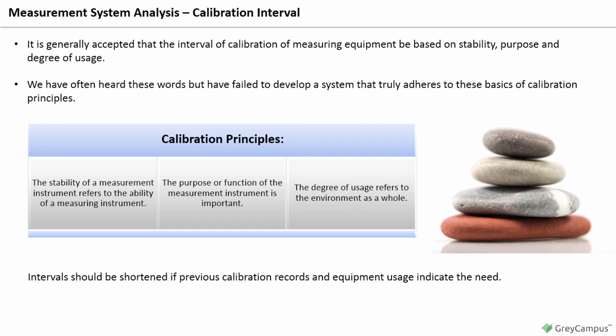A method gaining recent popularity is the verification methodology. This technique requires that very short verification frequencies be established for instruments placed into the system, i.e. shifts, days, weeks, etc. The philosophy behind this system is that a complete calibration will be performed when the measuring instrument cannot be verified to the known standard. This system, when utilized properly, reduces the cost associated with unnecessary scheduled cyclic calibrations.